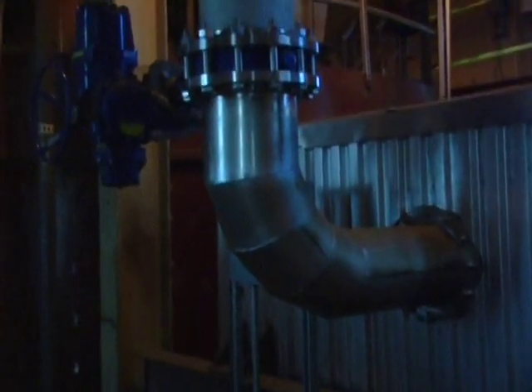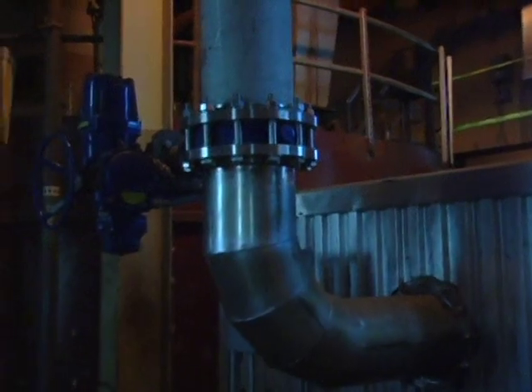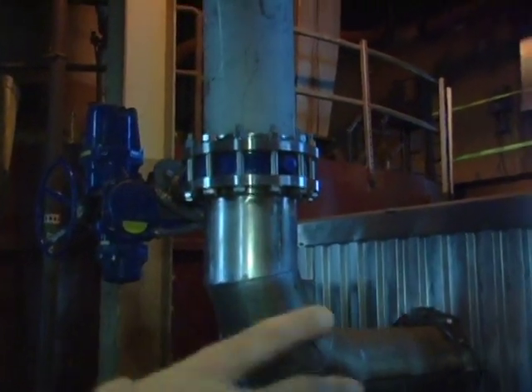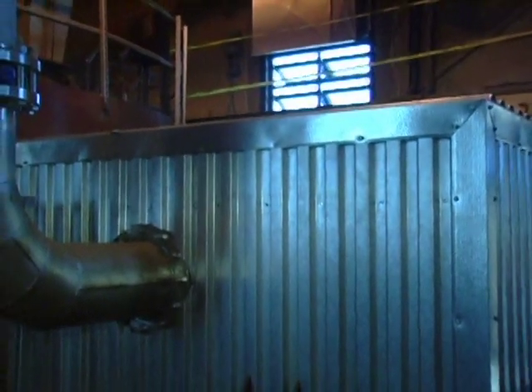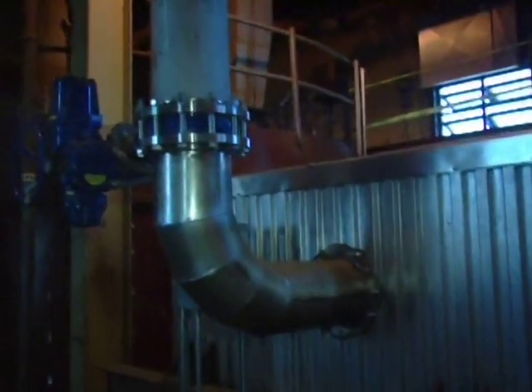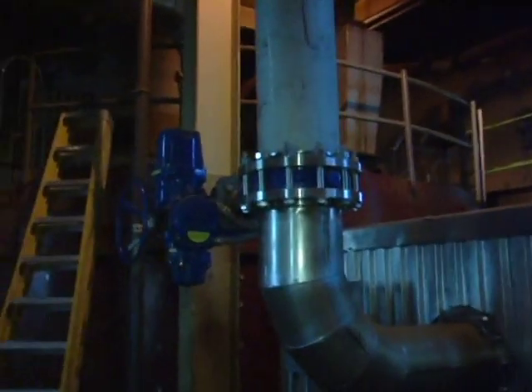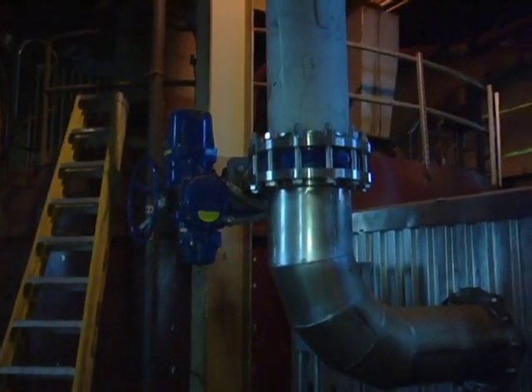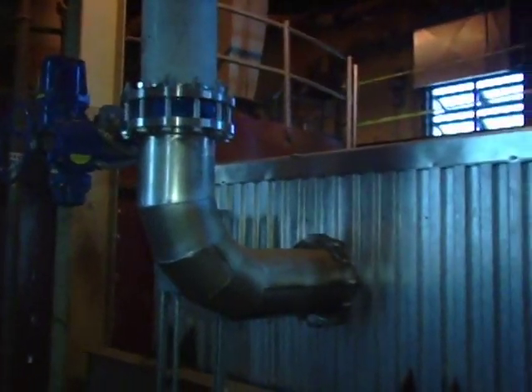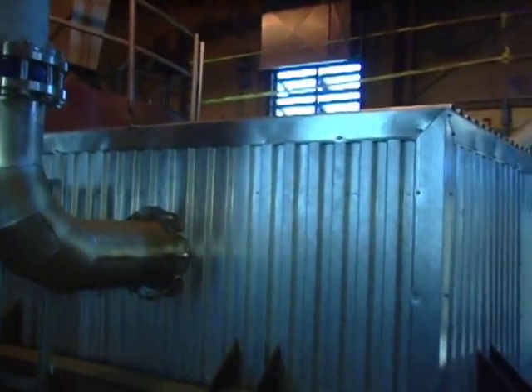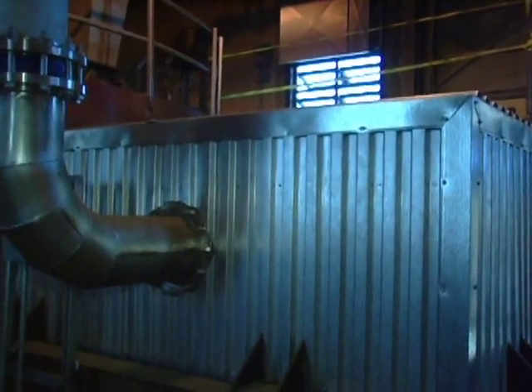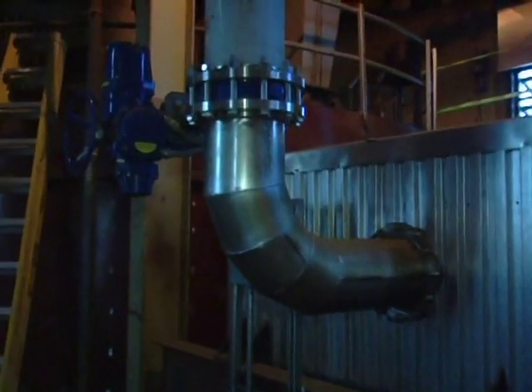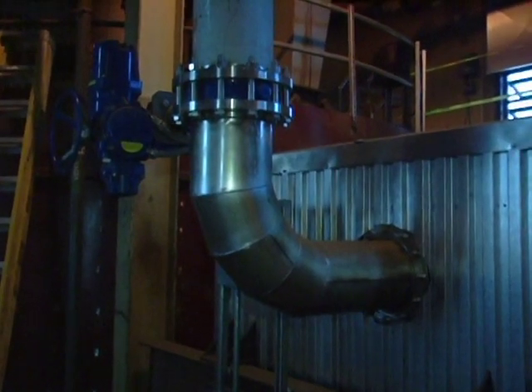Flue gas recirculation duct here, coming off the top of the furnace. Notice it's all insulated on the outside, and right here is where the odorous air comes in. We have an automatically controlled damper on the odorous air supply, so that can be changed and varied depending on the oxygen level in the flue gas. Okay. Does this valve modulate? Yeah, because you can adjust how much odorous air you put in. There's an expansion joint on the bottom here to allow the duct to expand and contract from the heat, because it's heating up a lot.